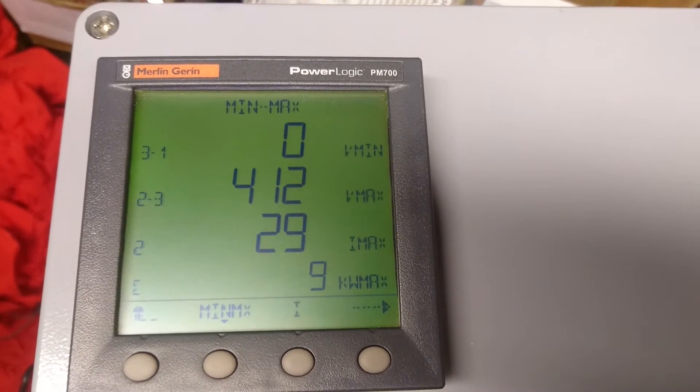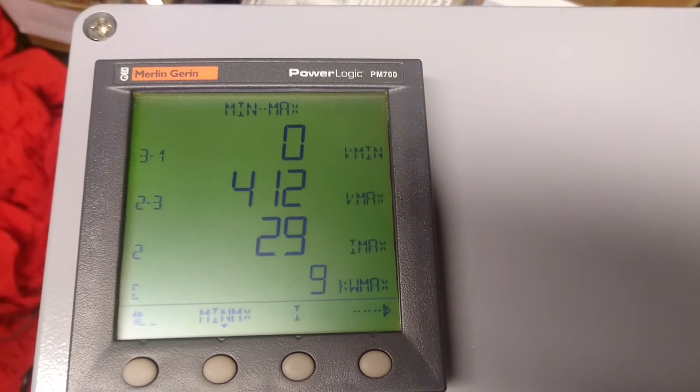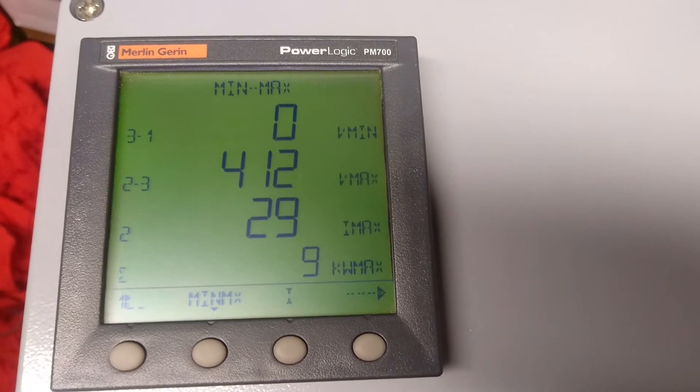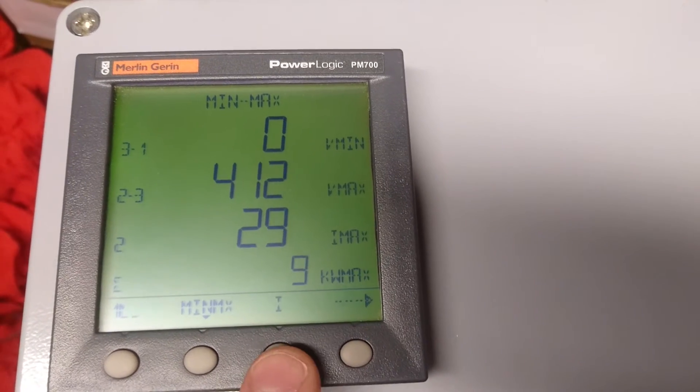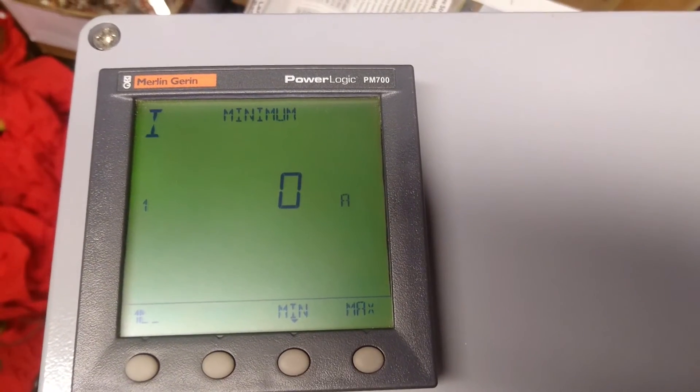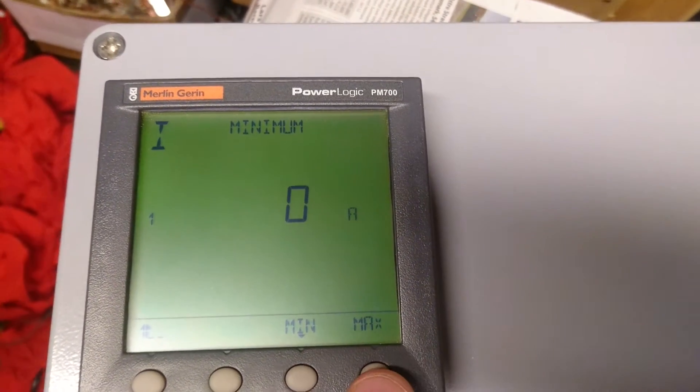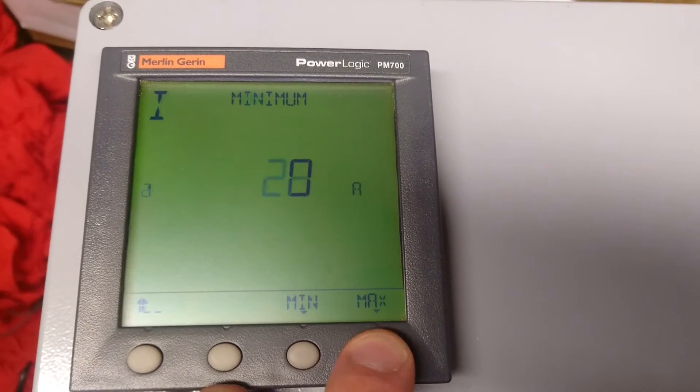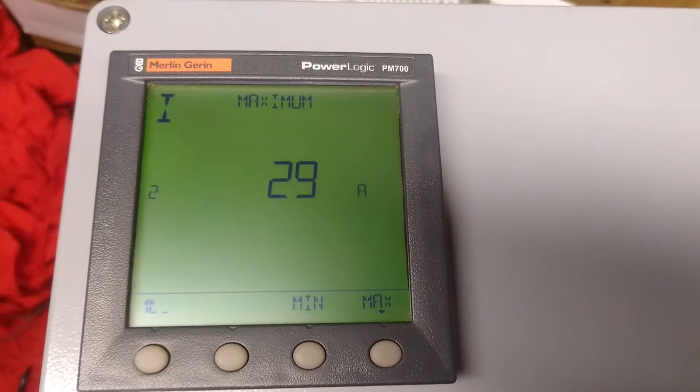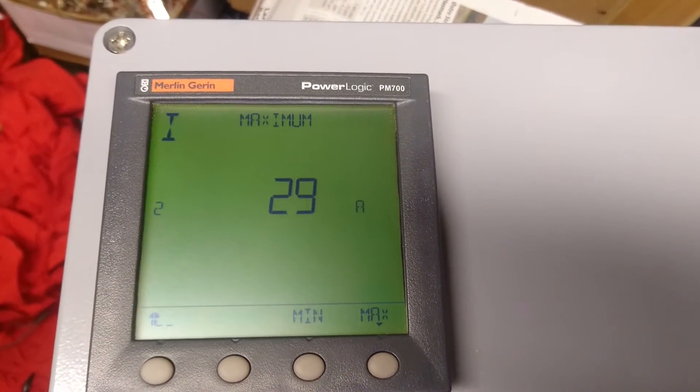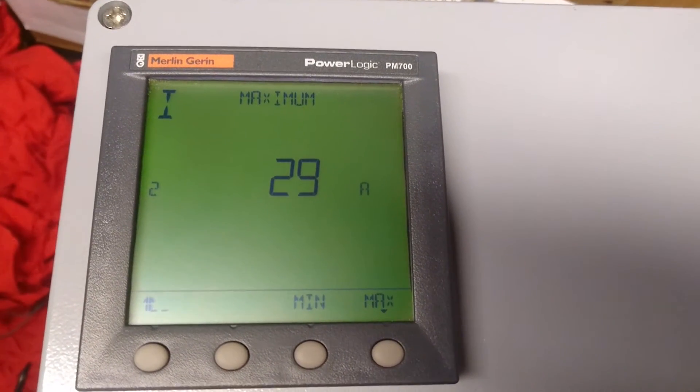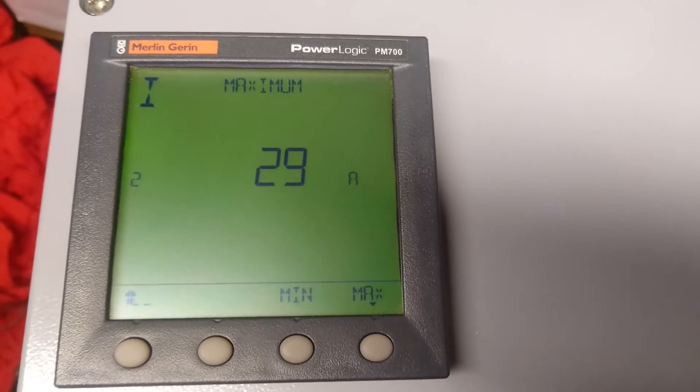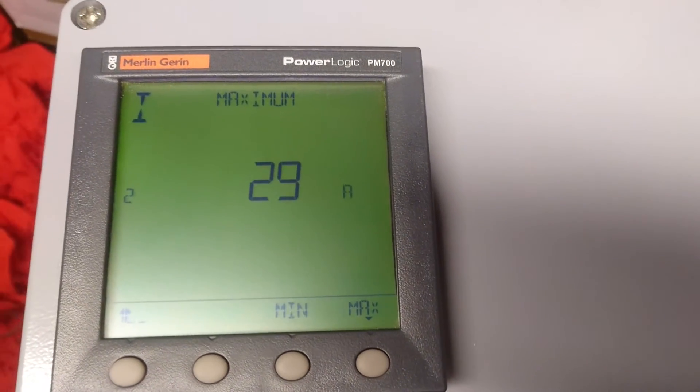It can also measure some minimum values, maximum values, minimum current draw and maximum current draw. So this is starting up the cold heating elements, it would draw 29 amps.